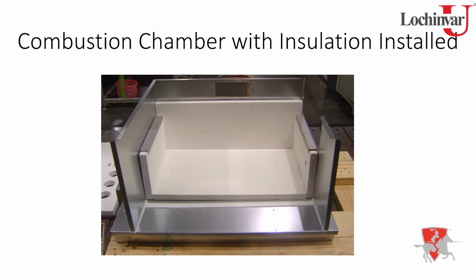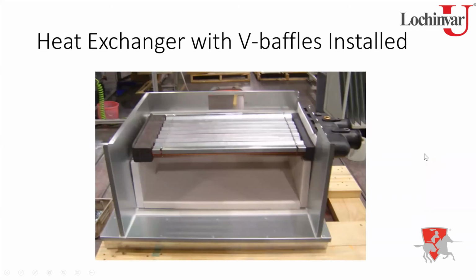So that way you can see the igniter, you can see the burners in operation, so you can see what's happening. Also, when you look over on the right-hand side, you see this U shape. This is where the heat exchanger sets down into. So when we go to this next slide, now we see that heat exchanger mounted down into the unit. As I said before, it doesn't slide out the front like we see with the other products. This one goes down from the top side. That front header will be attached or secured to the unit itself. So you'll see this insulation material that goes around the header. That's going to be used to seal that up at that point. You'll secure it with a few different screws to hold that nice and tight.